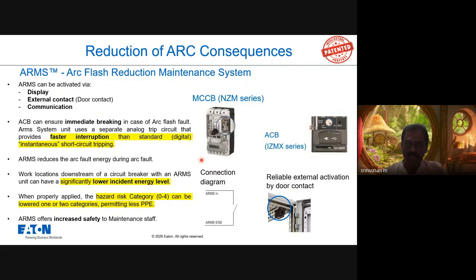Before carrying out that maintenance under live conditions, we enable the ARMS protection. Suppose an internal arc happens by mistake, due to dropping a torque wrench, a spanner, or a small piece of wire. This ARMS protection built into the breaker, whether it is an ACB or MCCB, clears the fault much faster than the instantaneous protection in the electronic trip unit. You might know that any thermal magnetic breaker or electronic breaker has the I function, instantaneous short circuit protection.